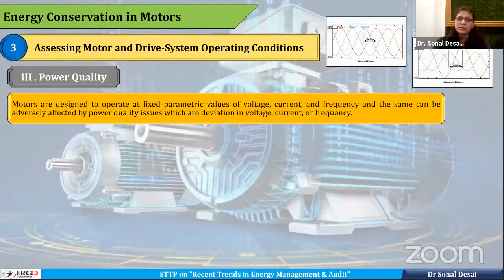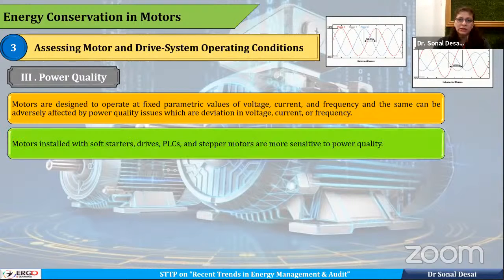A motor is designed to operate in a particular power condition. Say, for example, there should be certain parameters like voltage, current, frequency. At that particular condition, the motor should operate. And whenever there is a deformation or deterioration, the performance of the motor will also be affected. In particular, when the motor is used with a PLC or a soft starter, it is very sensitive to power quality. So we have to take care of that.